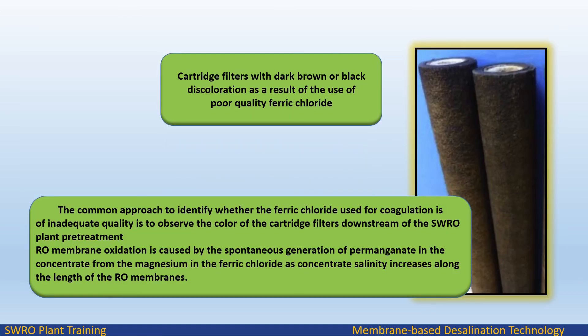Cartridge filters with dark brown or black discoloration result from the use of poor quality ferric chloride. The common approach to identify whether the ferric chloride used for coagulation is of inadequate quality is to observe the color of the cartridge filters downstream of the pretreatment. RO membrane oxidation is caused by the spontaneous generation of permanganate in the concentrate from the manganese in the ferric chloride, as concentrate salinity increases along the length of the RO train.